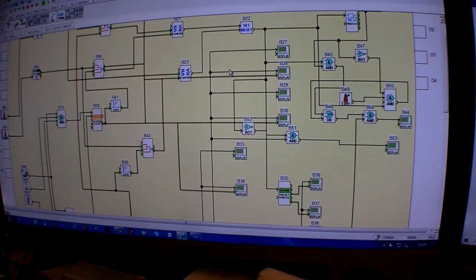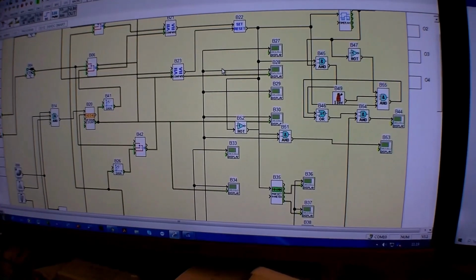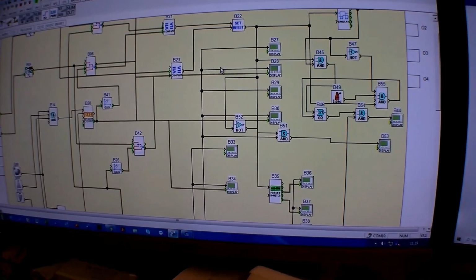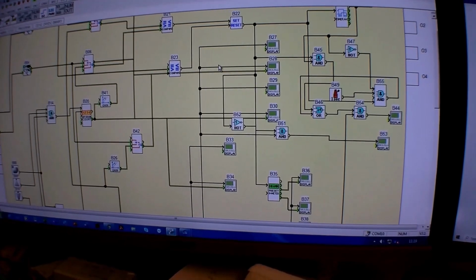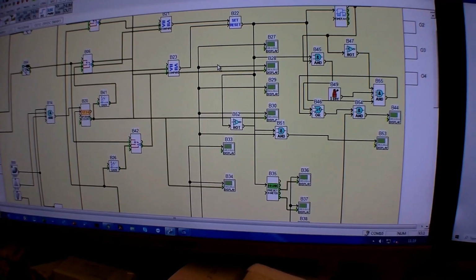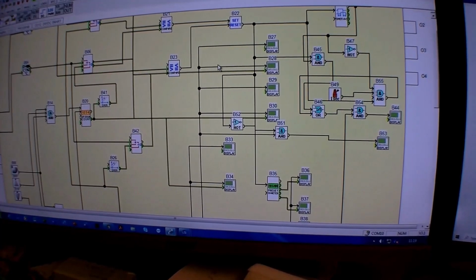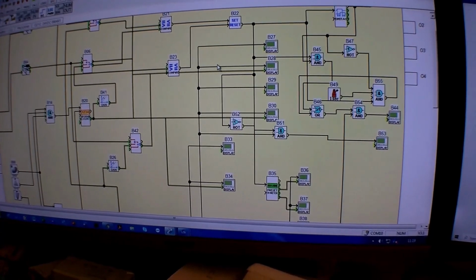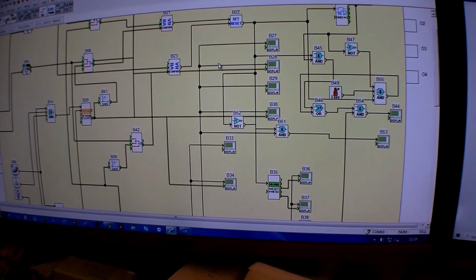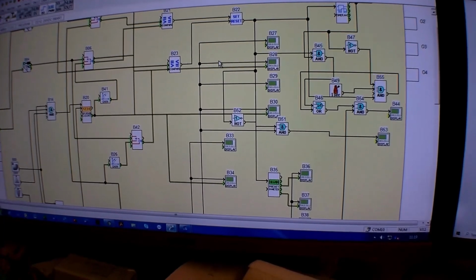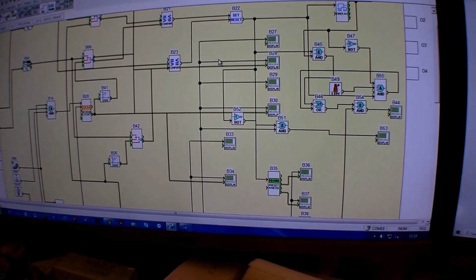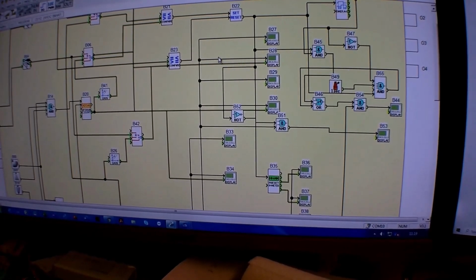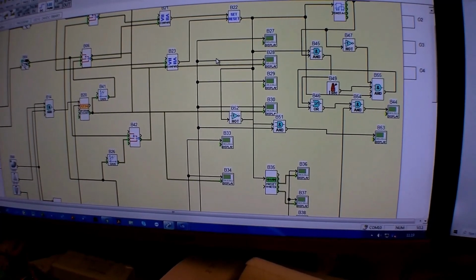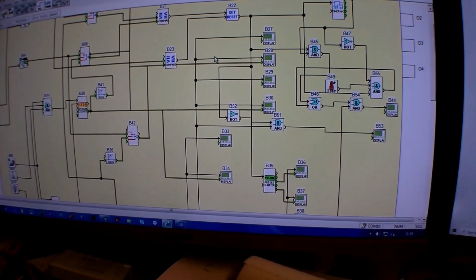This is a differential thermostat being used out in the Med by several companies. It looks at the roof temperature, looks at the tank temperature. You can set the differentials that you want in each of the flows. You can set your maximum temperature, and it does what we've been asked to make it do. And there's several of them working out there. In fact, quite a lot of sites working out there. It gets quite warm actually.